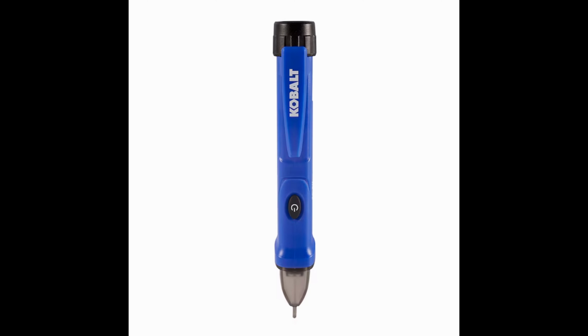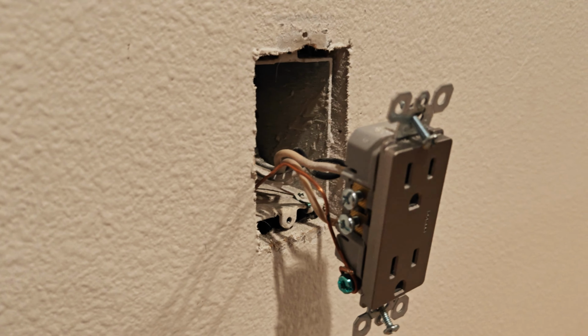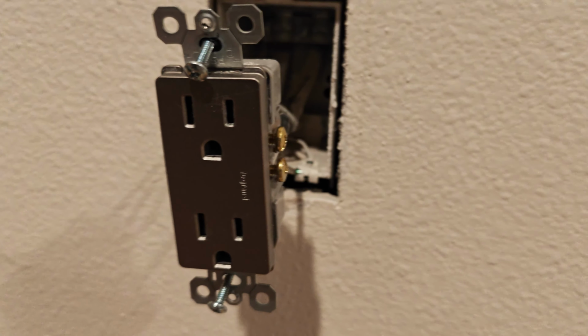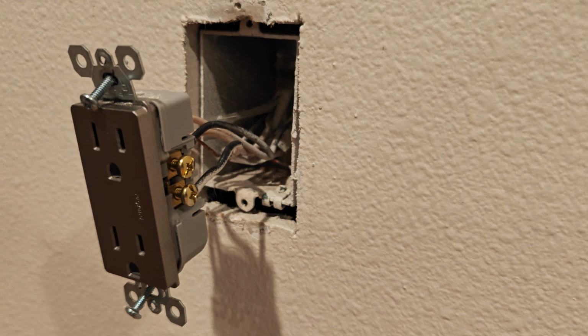First, remove the faceplate. Most are held in by a single screw in the center, but as you can see here, this one is a snap-on, so we'll just pop it off. Next, remove the mounting screws at the top and the bottom. Pull the receptacle out. There should be ample lead on the wires to pull out, just far enough for you to work, but not always. Sometimes it's a little bit of a hassle, but do the best you can.